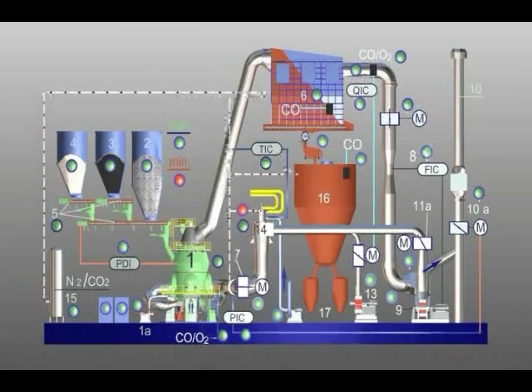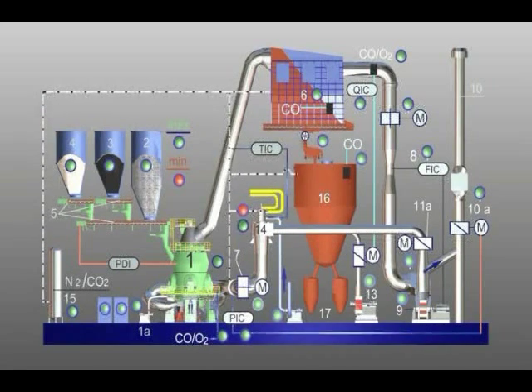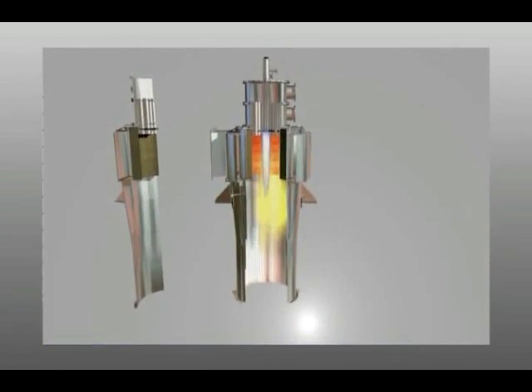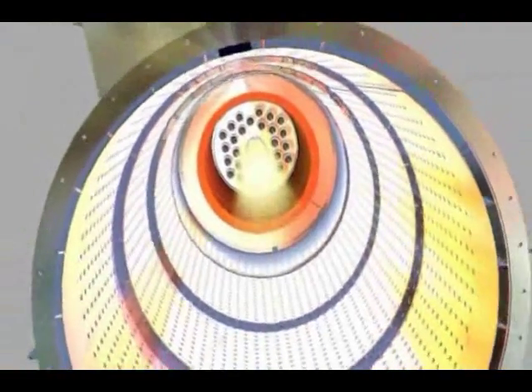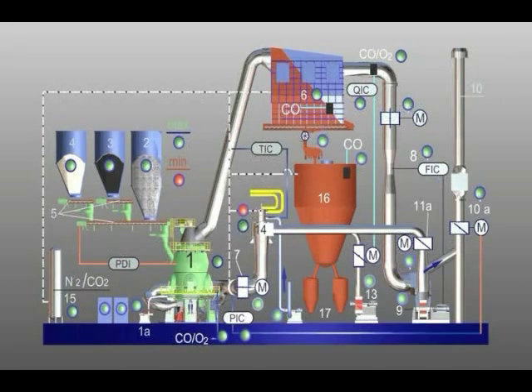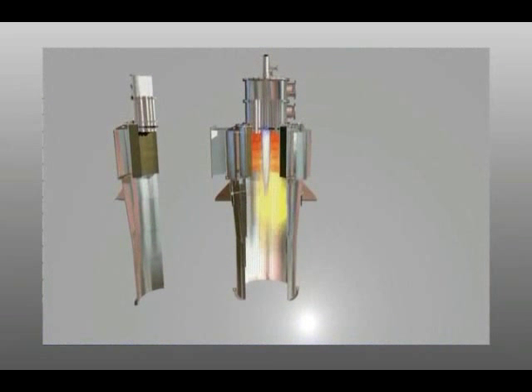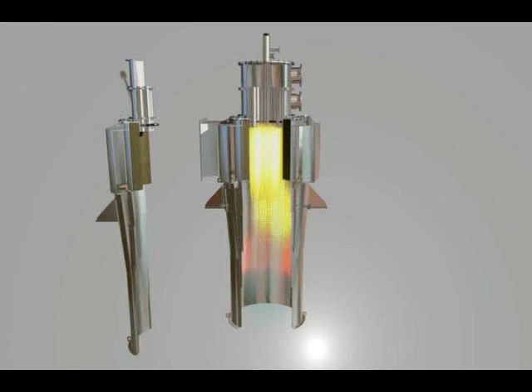Inert gas is still being fed into the plant. The hot gas generator consists of a main burner for blast furnace gas, synthesizing gas, etc., with a coaxially integrated start burner for coke oven gas or natural gas. The start burner fulfills various functions. It serves to warm up the combustion chamber muffles to temperatures of over 350 degrees Celsius, and the entire plant to temperatures higher than 65 degrees Celsius. When these two preconditions are met, the main burner is enabled.